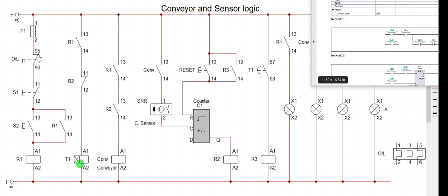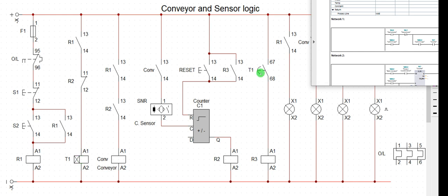So R2 does two functions: R2 activates the timer and R2 deactivates the conveyor. R2 is an integral part of this relay coil. When that sequence is completed, the timer gets energized. Upon completion of the preset time, the timer activates a relay. Look at the timer — this timer will activate a contact, and when the preset time is completed, it activates a relay that will reset the counter, just as the PLC logic did by reloading the value.